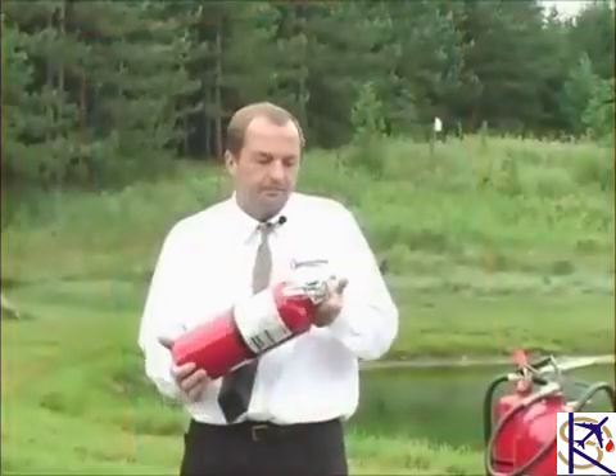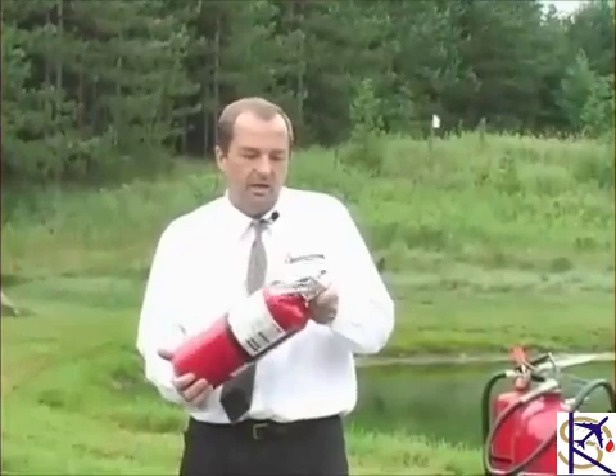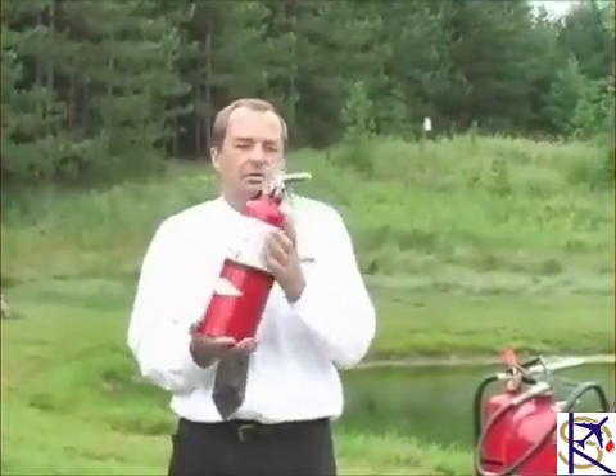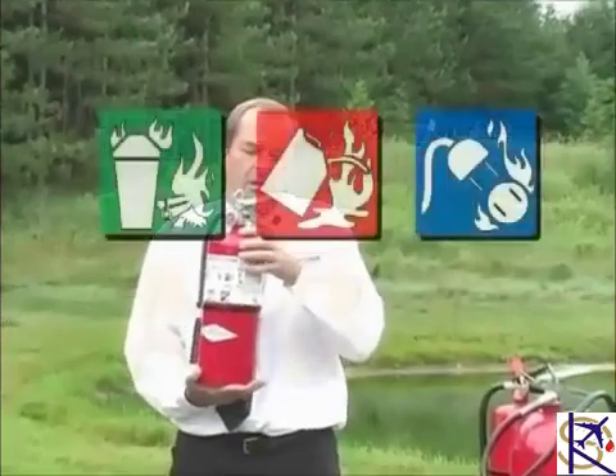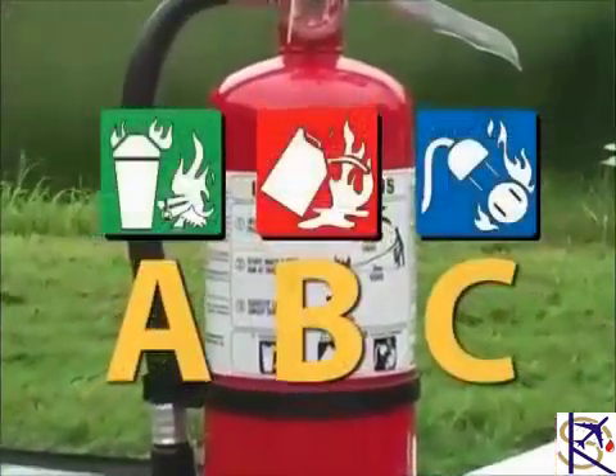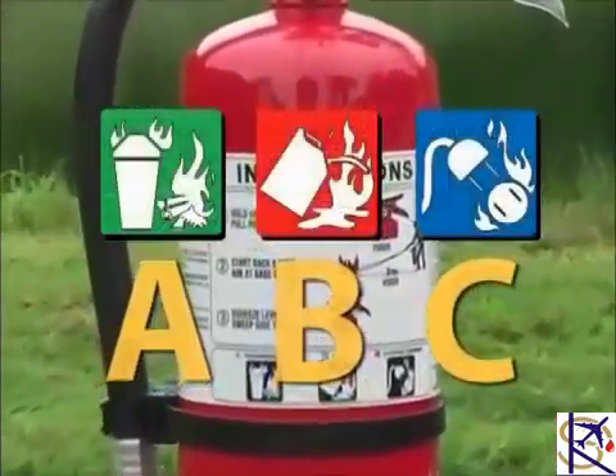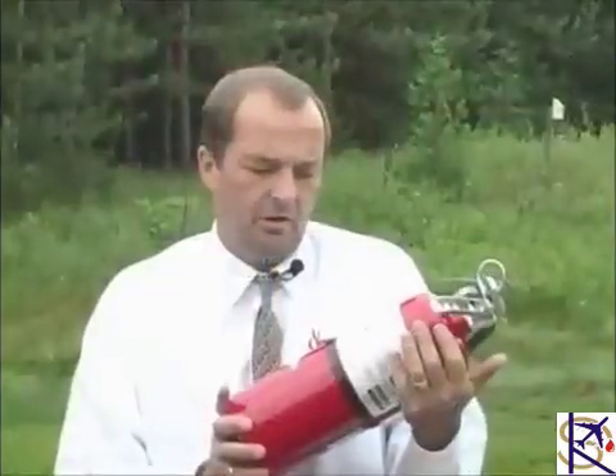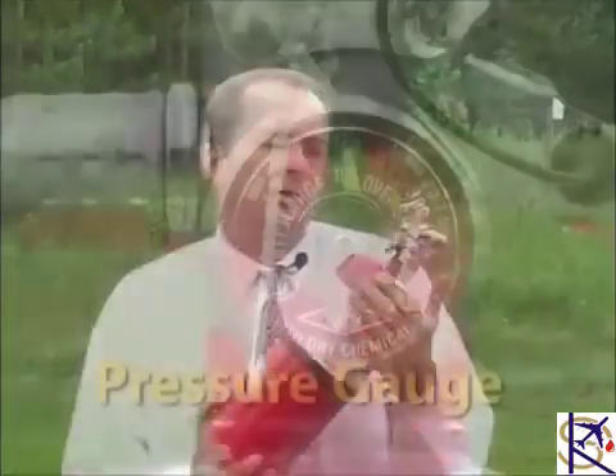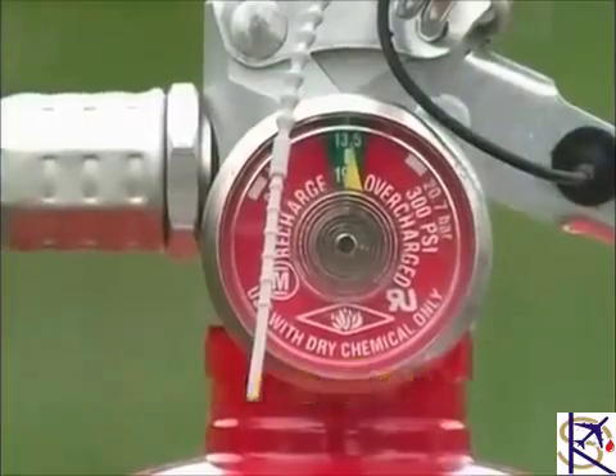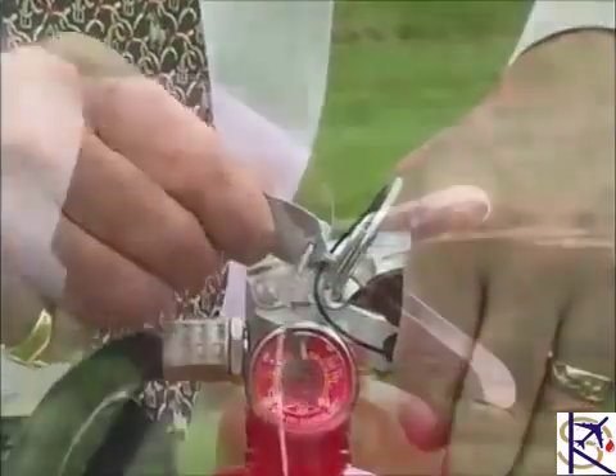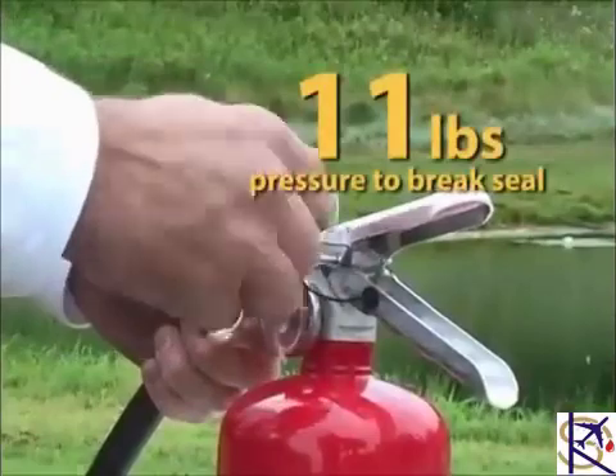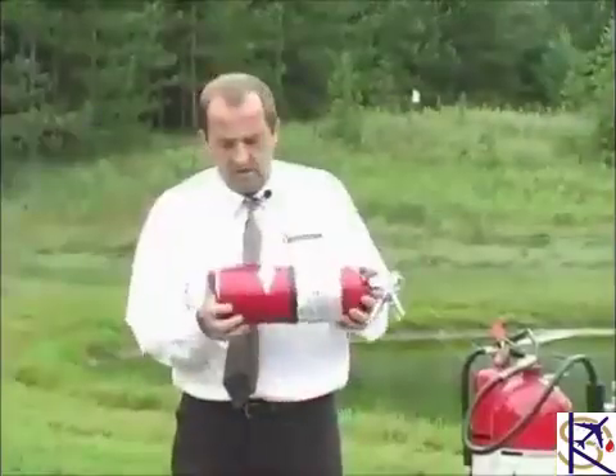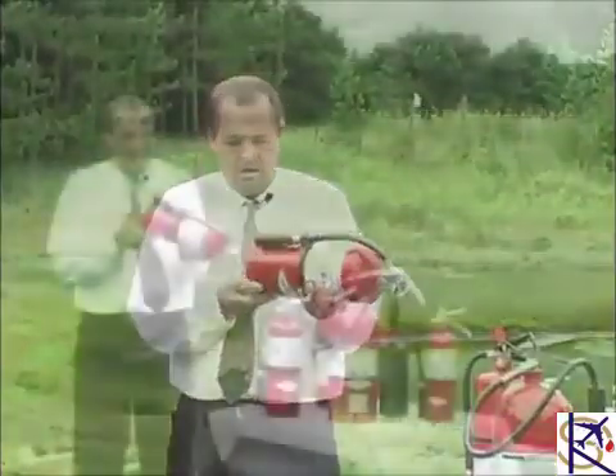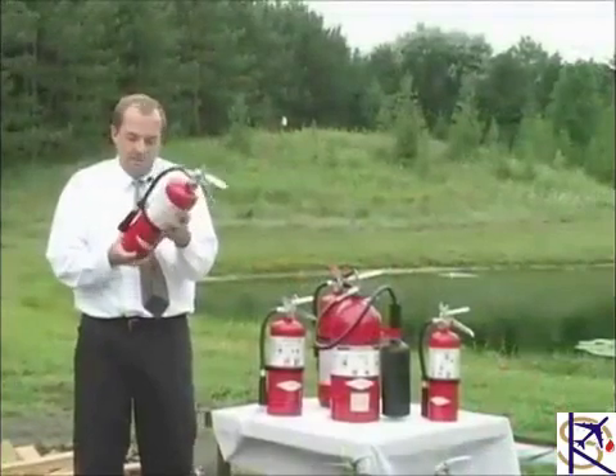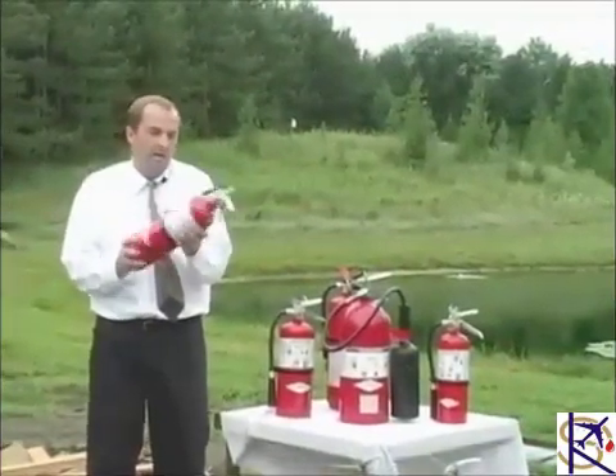The first thing I'll talk about is an ABC fire extinguisher, multi-purpose. This particular extinguisher is made by Amerex, a top quality extinguisher, pressurized, with a pressure gauge and a tamper seal on it. It takes 11 pounds of pressure to break the tamper seal. It has a steel shell, and this particular one was made in 2005, dated.